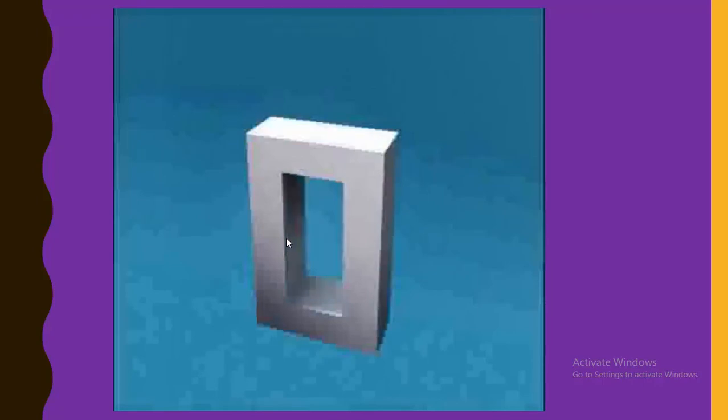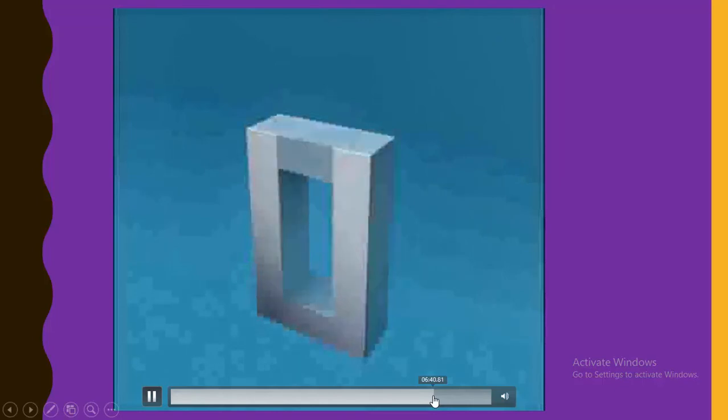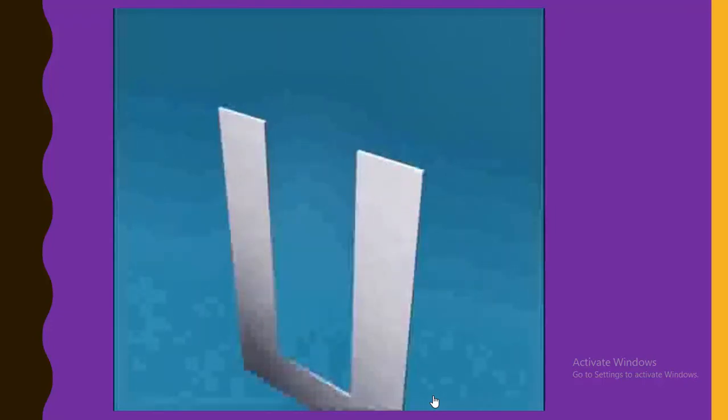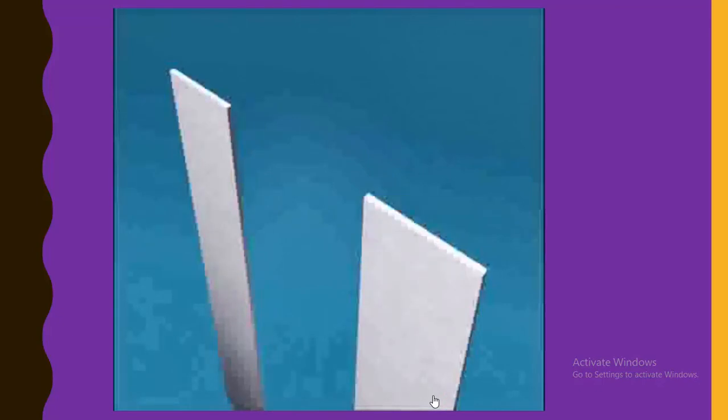Laminations are made up of a highly permeable material, that is silicon steel. The resistance of the steel sheet itself is high, reducing the eddy current losses while making the laminations very thin. The thickness of these laminations varies between 0.25 mm and 0.5 mm, and as steel is a conductor, the laminations are electrically insulated from each other by a very thin coating of insulating varnish or by an oxide layer on the surface.